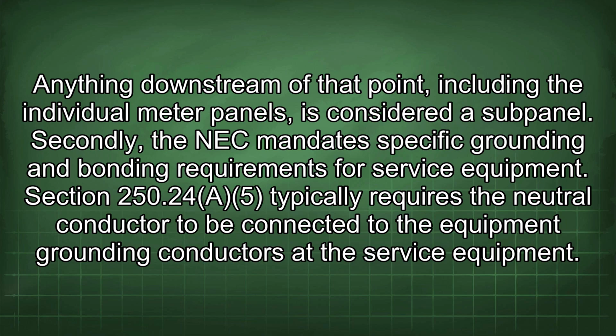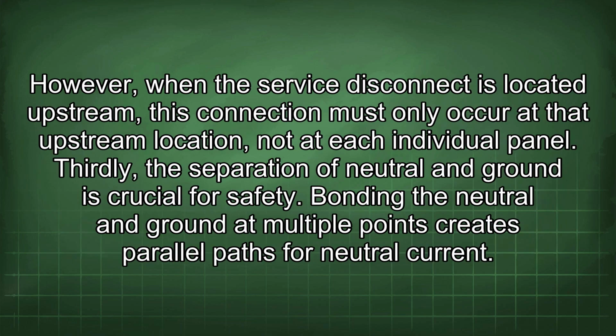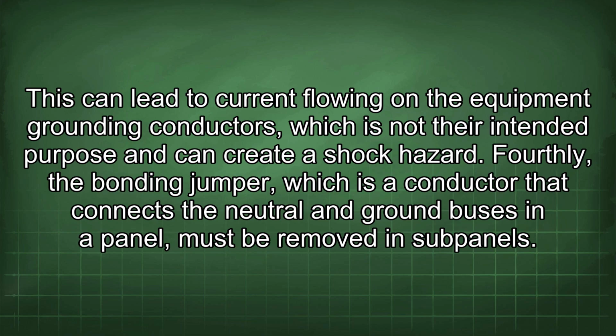Secondly, the NEC mandates specific grounding and bonding requirements for service equipment. Section 250.24 typically requires the neutral conductor to be connected to the equipment grounding conductors at the service equipment. However, when the service disconnect is located upstream, this connection must only occur at the upstream location, not at each individual panel. Thirdly, the separation of neutral and ground is crucial for safety. Bonding the neutral and ground at multiple points creates parallel paths for neutral current. This can lead to current flowing on the equipment grounding conductors, which is not their intended purpose and can create a shock hazard.